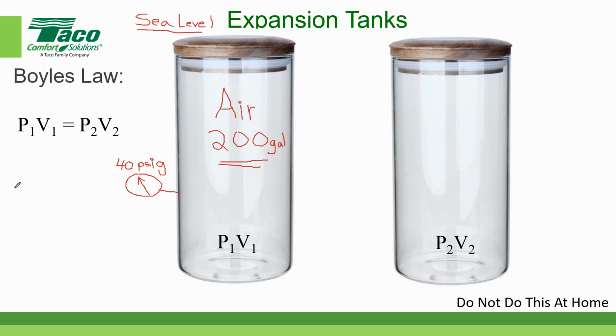The way we get that is we say that one atmosphere, ATM, in units of pounds per square inch, at sea level has a pressure of 14.7 PSIA. To convert gauge pressure into absolute pressure, I have to add that 14.7. One atmosphere equals 14.7, so someone did say that correctly. So 40 plus—I'll put a little arrow here, plus sign—40 plus 14.7 is 54.7. We had someone round it off to 55, so that's not too bad—I'll give him credit too. You can use 55 for tonight's discussion, so 55 PSIA.